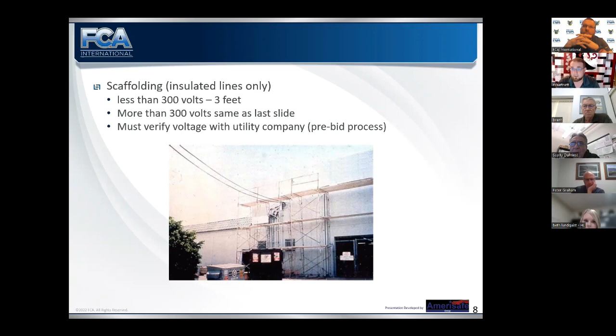We're allowed to set up scaffolding 3 feet away from insulated lines below 300 volts. But once again, this is part of your pre-bid process. You need to know what the electrical hazards are on the sites so that you can make sure you have the right budget to be able to execute and still make your profits. Because if we give that short budget, what are our employees going to do? A lot of times, if we're not giving direct instruction, they'll get closer than they need to, closer than they should to get the job done.